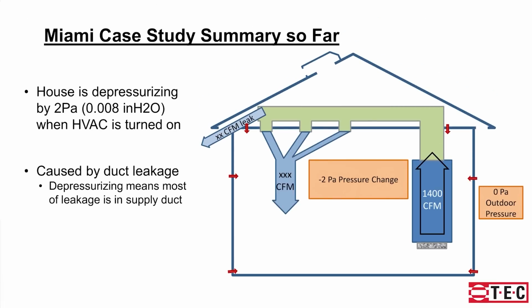Okay, so here's what we've measured. If the house goes minus 2 when the system runs, here's what's happening. The HVAC system is pushing 1,400 CFM up through the attic. This system had no return ducts in the attic. The return is just a filter on the bottom of the cabinet in the living space. So all the HVAC ductwork is on the supply side that's in the attic. So 1,400 CFM leaves the house, goes into the attic, and some amount of it leaks out, and some amount of it comes back in.